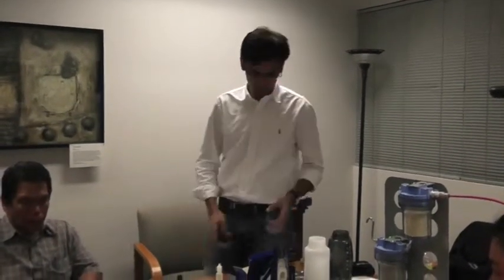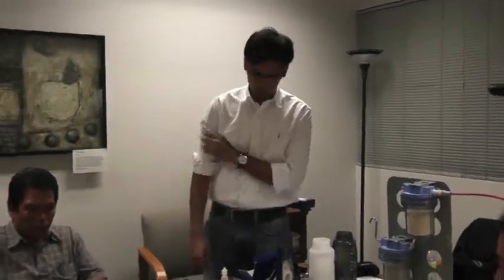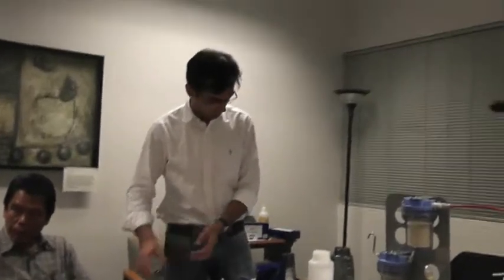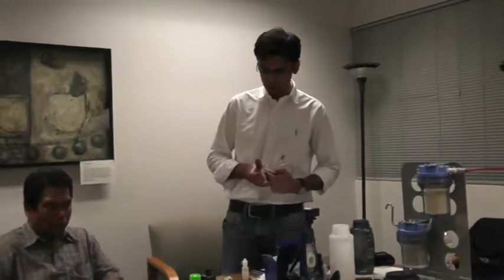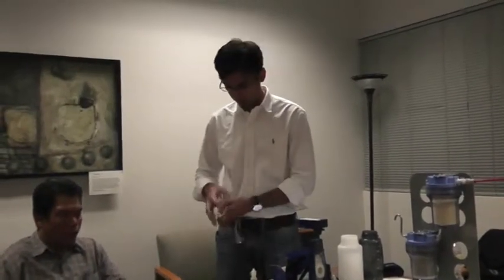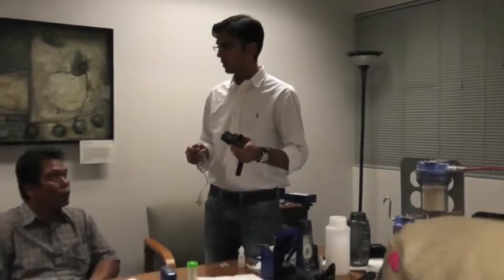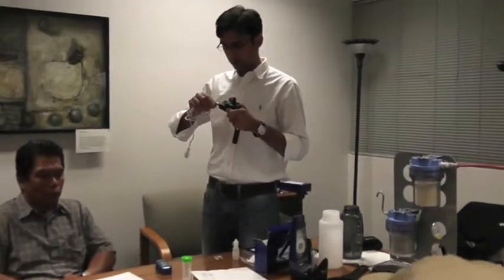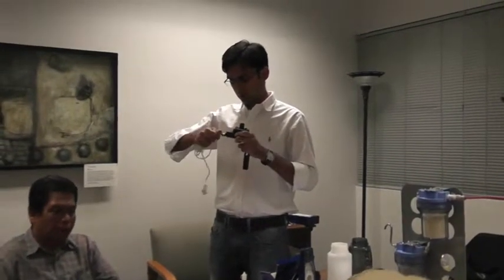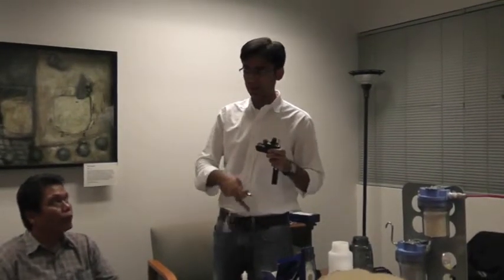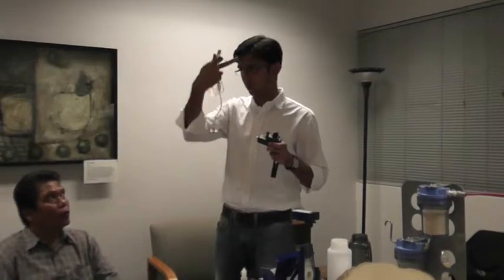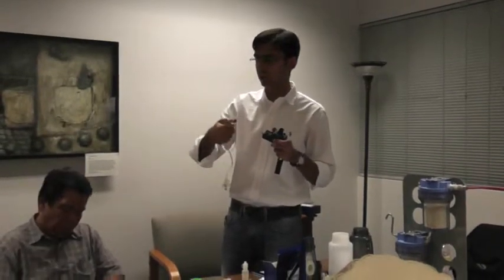That AirLink thing or whatever, it's all set, once you put this one in. What is this, the phosphate that you're doing? This one is nitrate. Nitrate, okay. For the nitrate one, do we have to recalibrate? It's already calibrated. For nitrate, nice, all you have to do is put that in and get a reading. Yes, but select the right measurement. Okay, that you're in nitrate. On the drop-down list, you got to select the measurement, and that's nitrate.